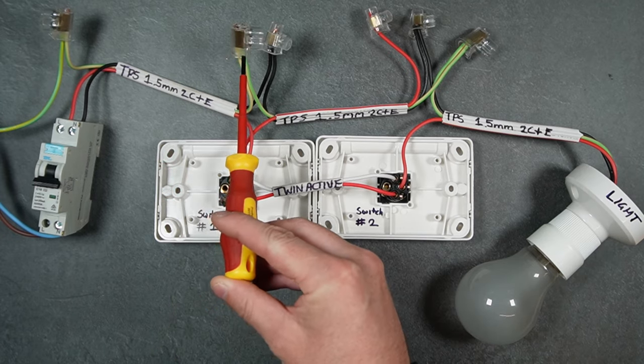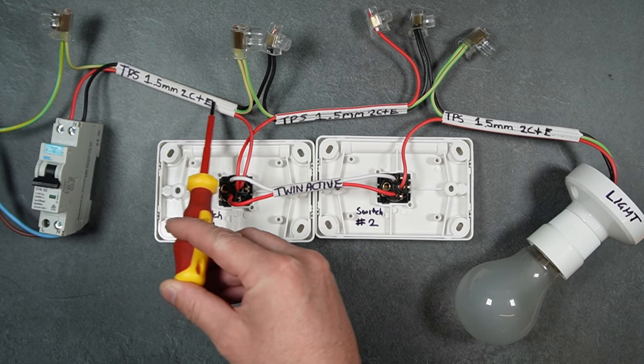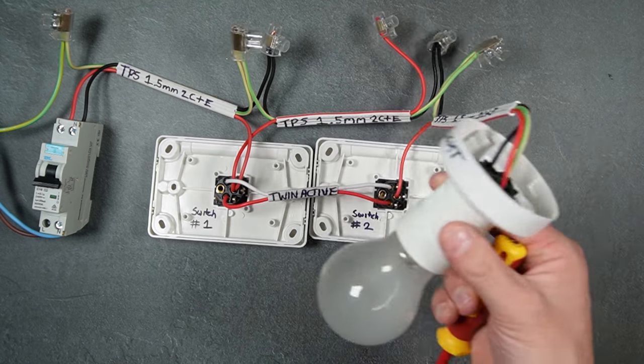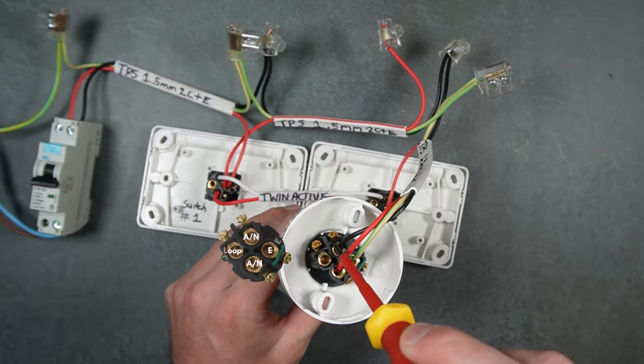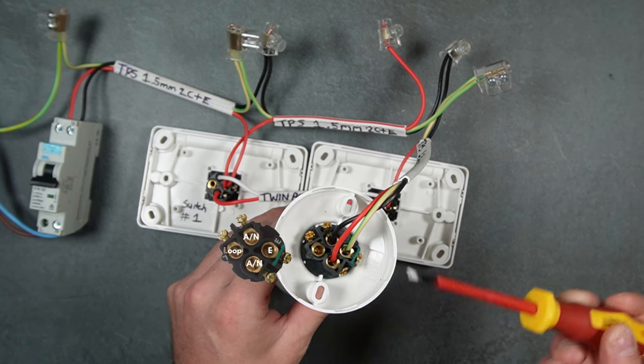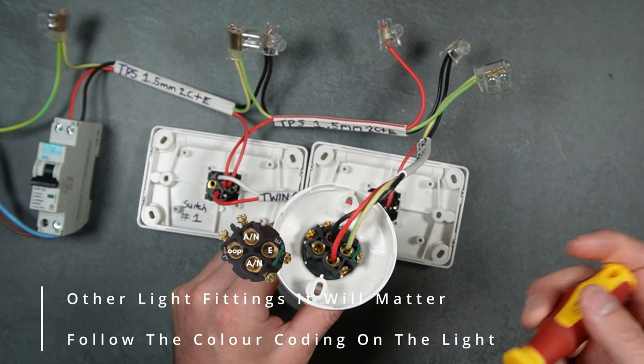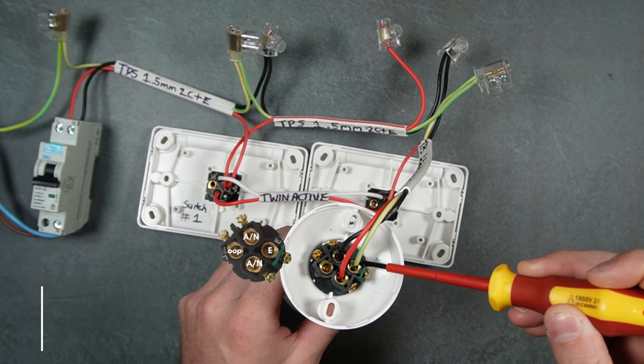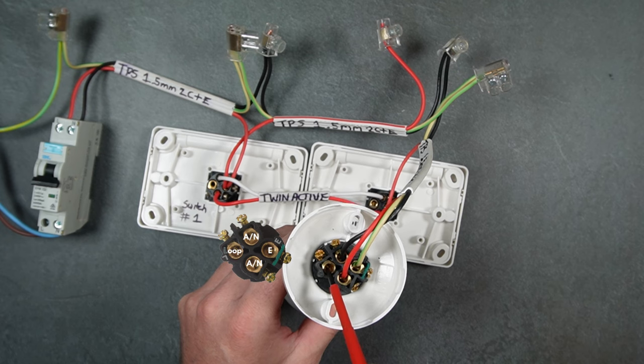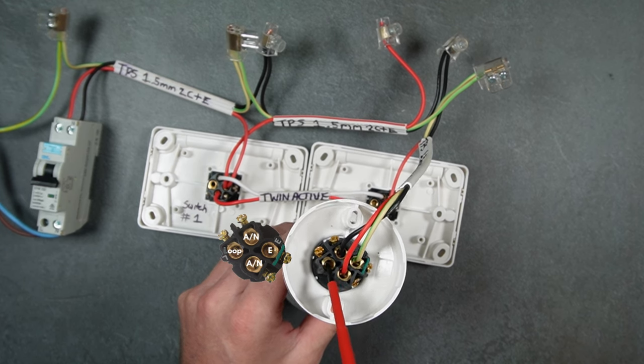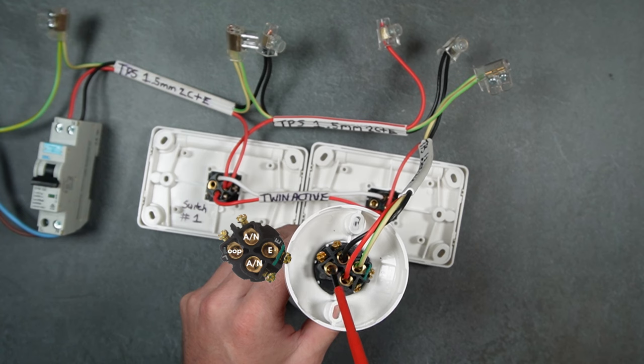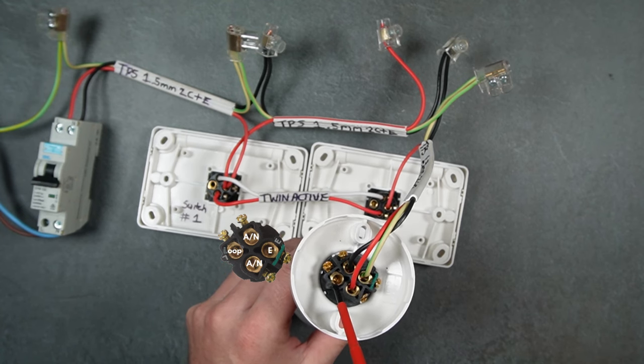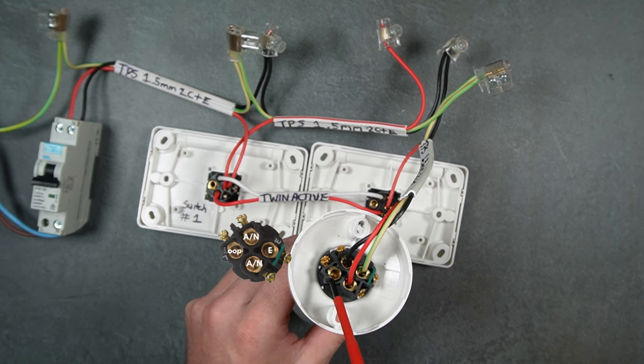These are the terminals on the light - active and neutral. It doesn't matter which one you use for active or neutral on a batten holder. Your earth is clearly labeled. And the loop-in terminal is just a dead terminal, and this would be used just to join cables - acts like a connector, pretty much - and it would be used in the looping at the light method.